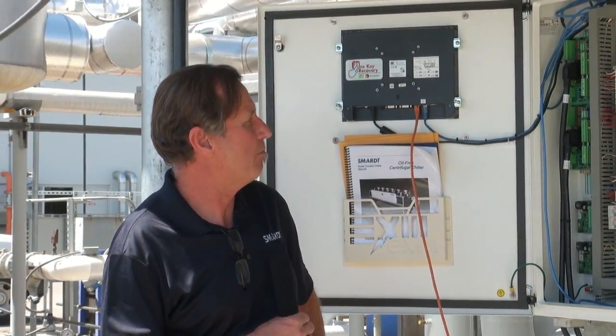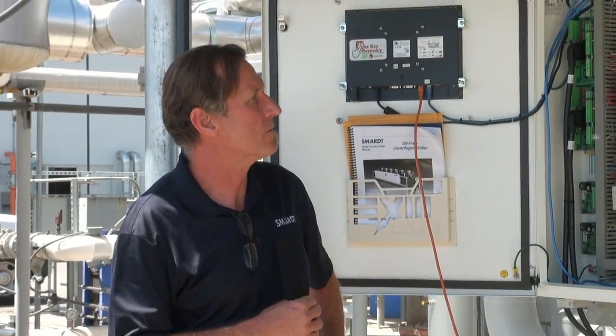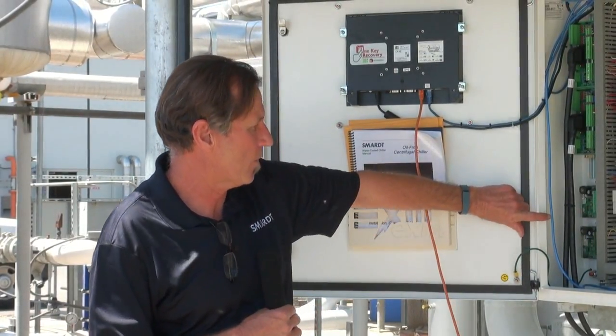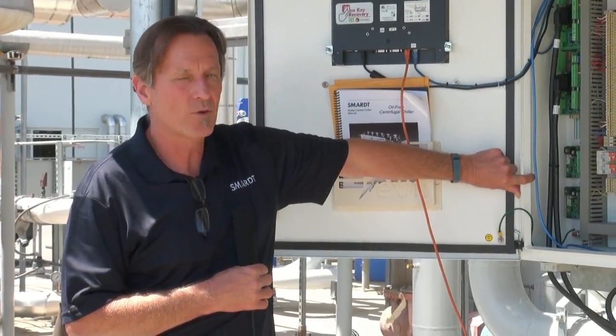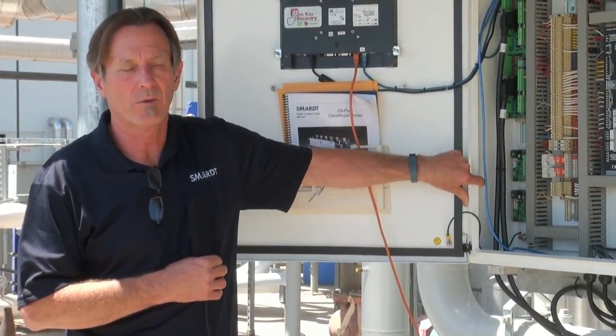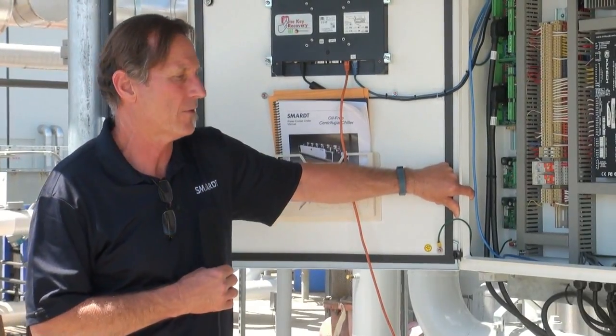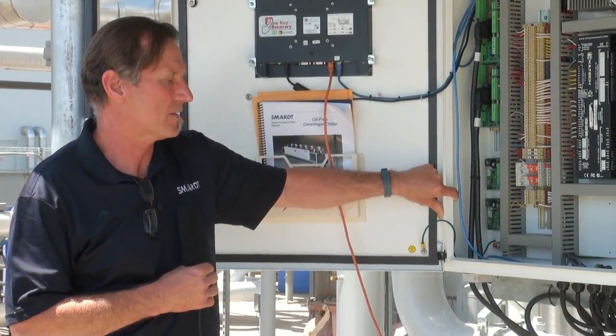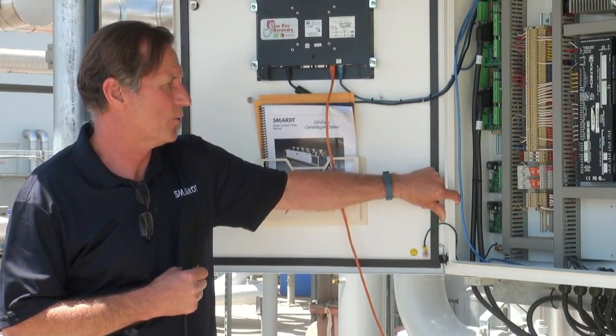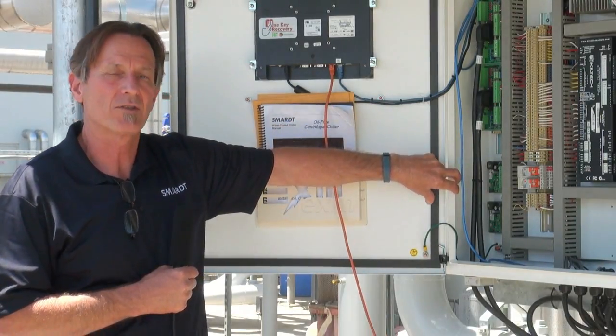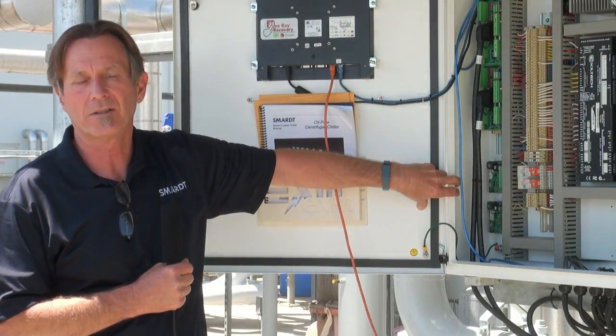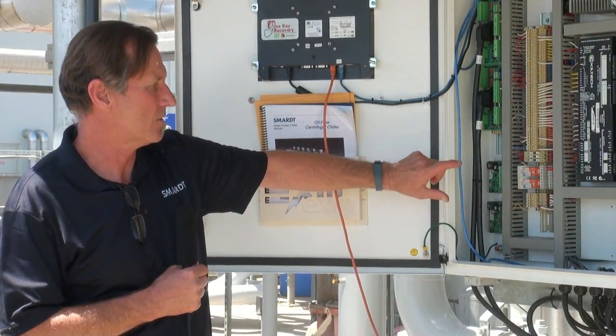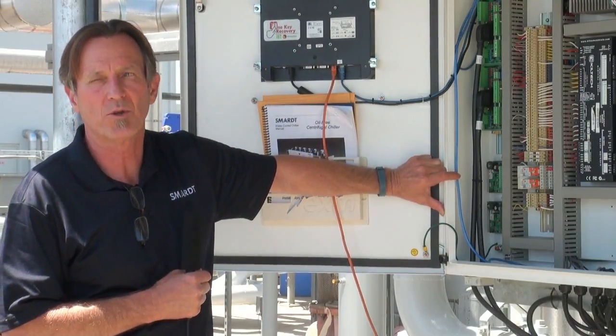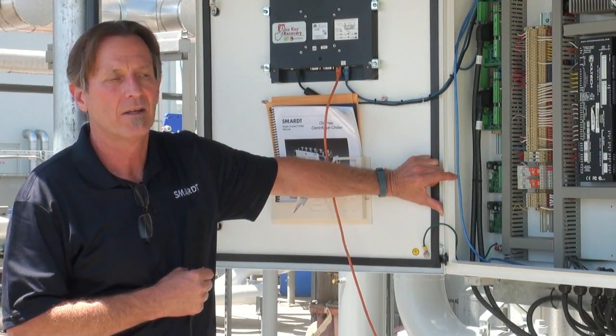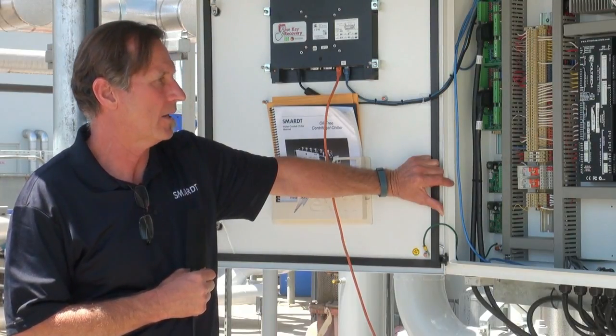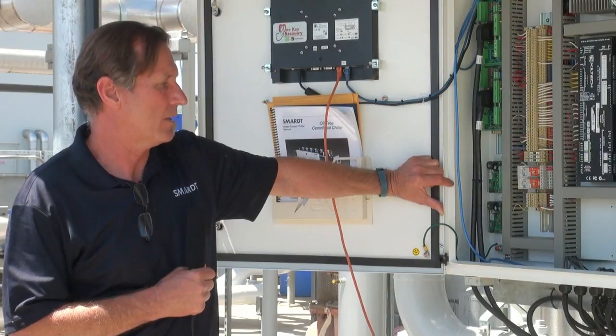So that's the basics in the panel. That's the major components. We've got a couple of other boards here on the lower left, and those are driver boards for the expansion. Well, one's for the expansion valve, the other's for the hot gas valve. So those are electric valves that are driven off the controller. It sends over a 0 to 10 volt signal to these boards, but these boards actually do the driving. They have the power to run the valve, but it's still under control by the controller.